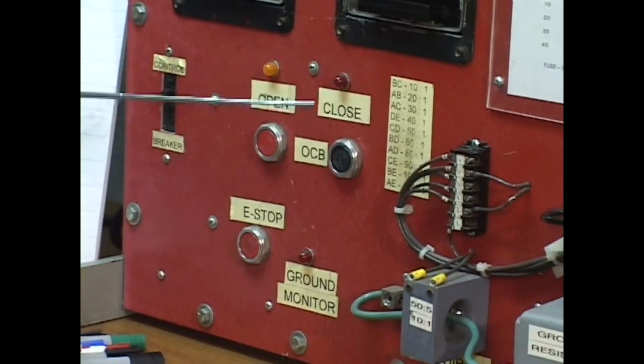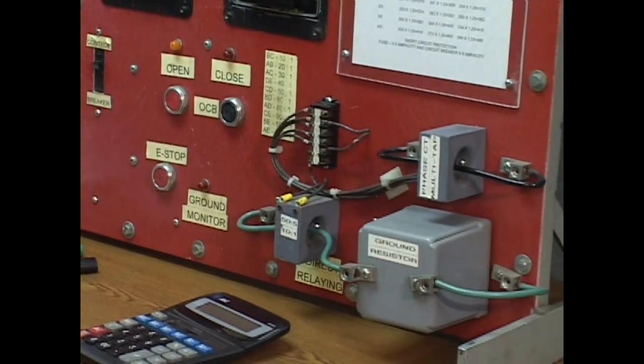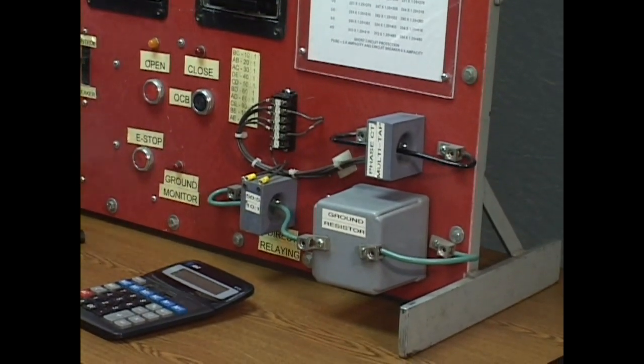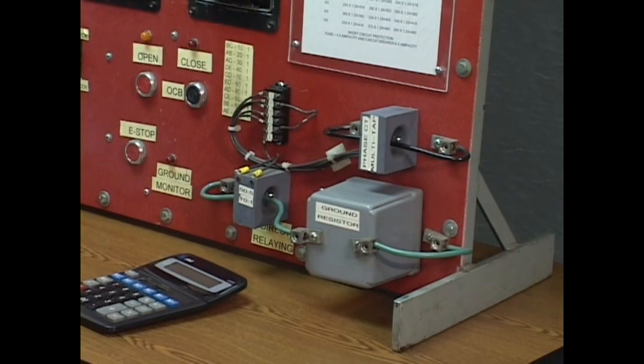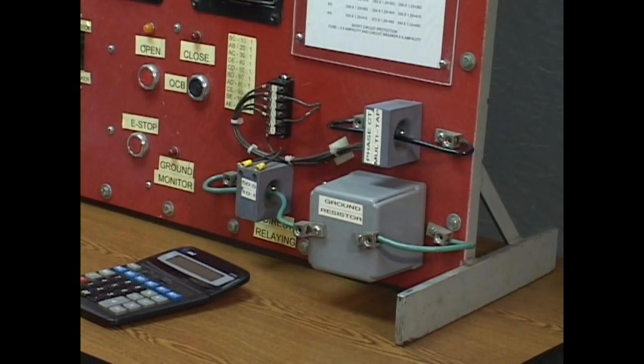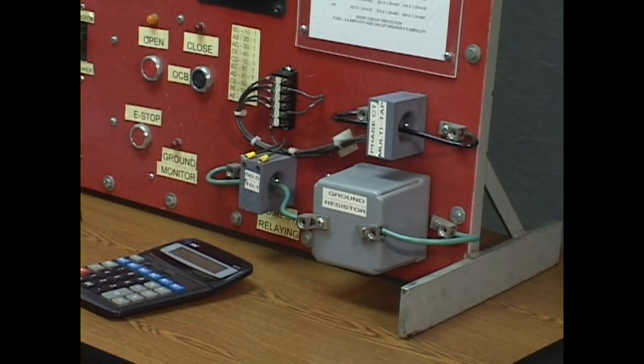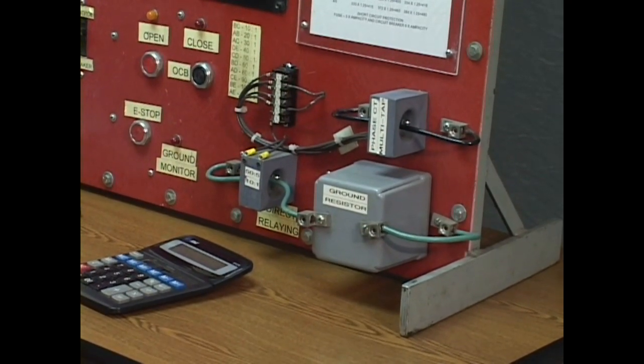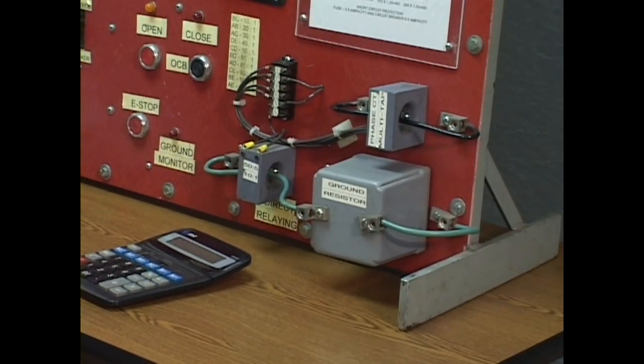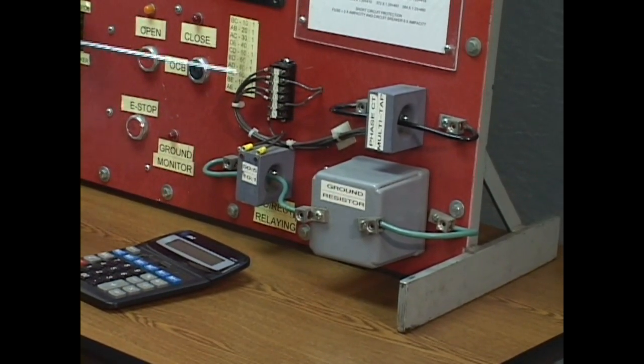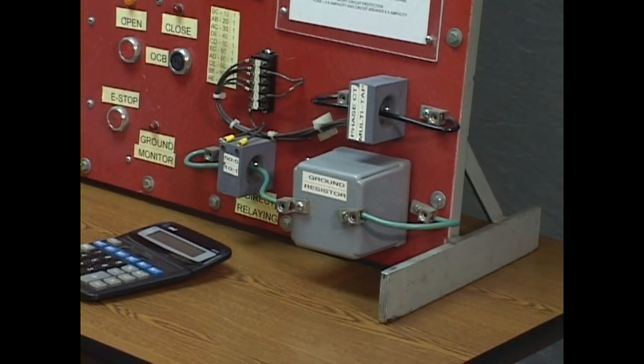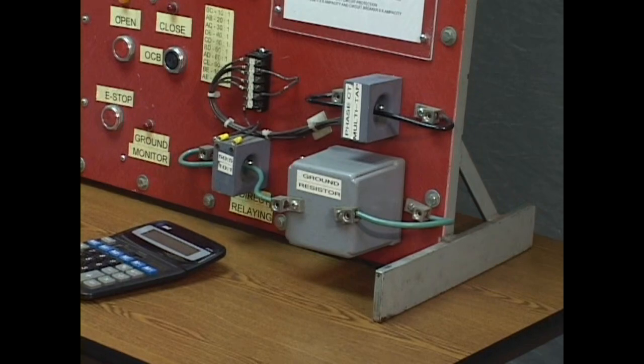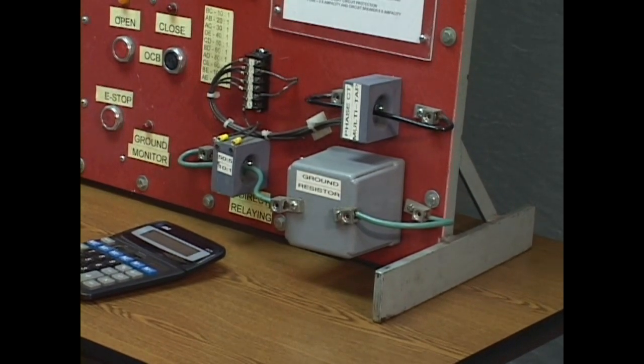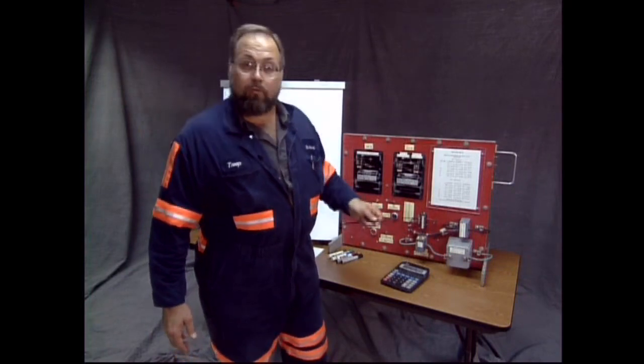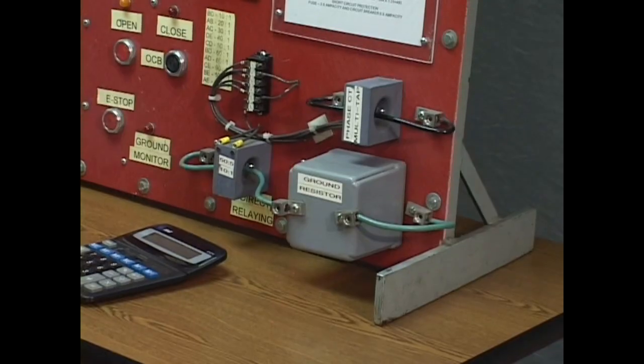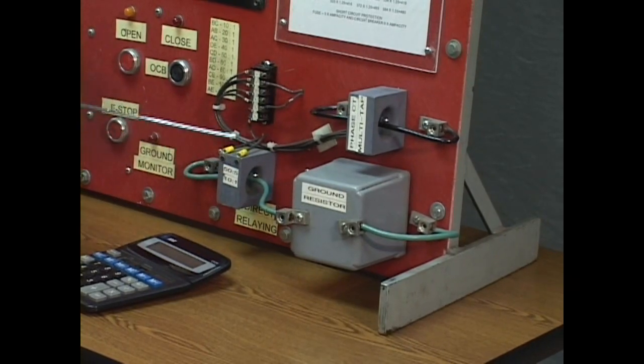Now we have a ground resistor at the source of all of our power circuits. The ground resistor, that's our number one safety device. It protects you in the event of an insulation failure that involves a phase, an energized conductor, coming in contact with the frame of any piece of equipment or the ground conductor on any cable. The ground resistor is going to resist the current. It's going to be an obstacle to the flow of current and limit the current because it's in series with the neutral of the transformer. It will limit the current to 25 amperes maximum, okay? And the voltage drop external to the ground resistor.